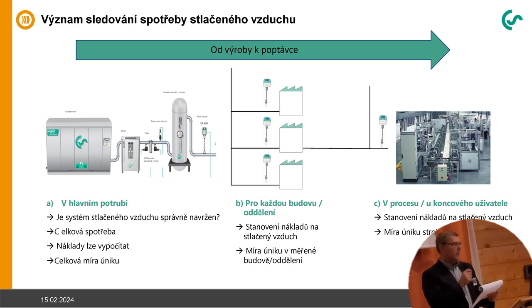And on the right side, we can see, let's say, the process or the machine where the compressed air is needed. And if you install a flow meter in front of the process, you can allocate the costs to the products which you produce. So let's say if you produce, for example, cement, you can say per 1 ton of cement we need compressed air for 10 euros. Or if you produce screws, per 1,000 screws, we need compressed air for 100 euros, and so on and so on.